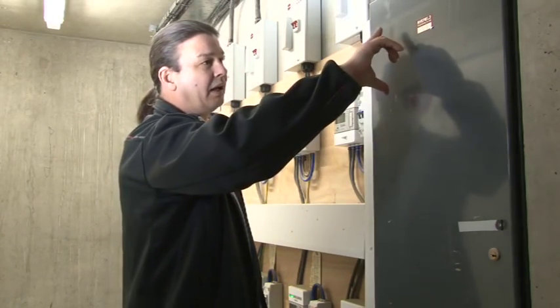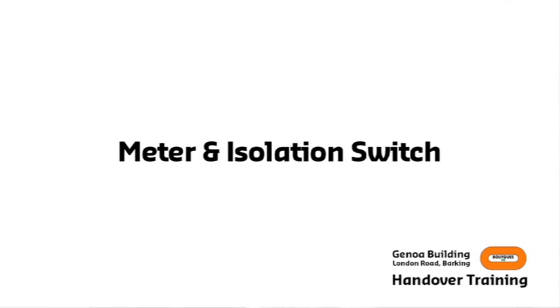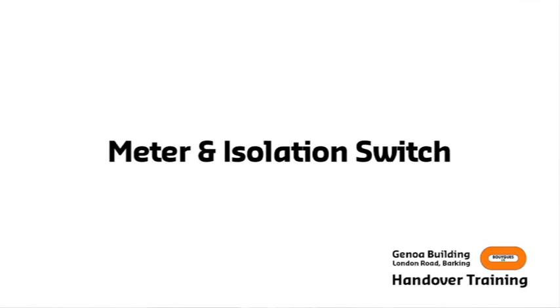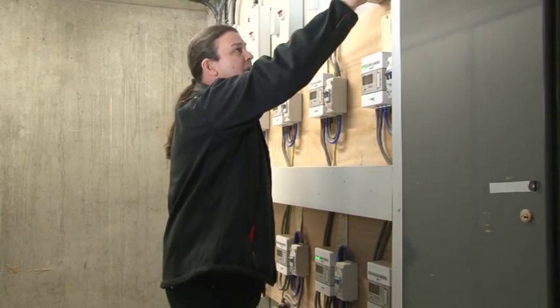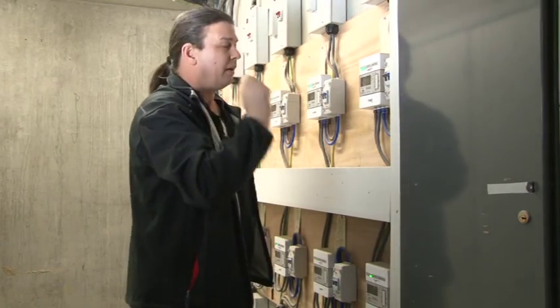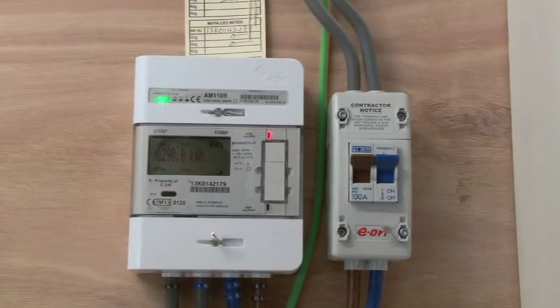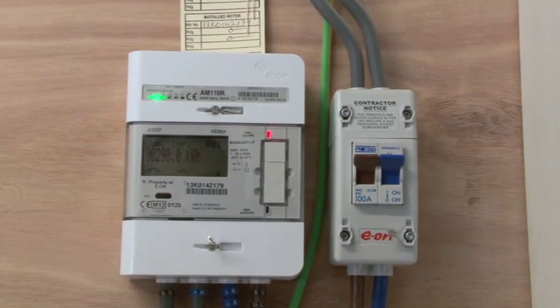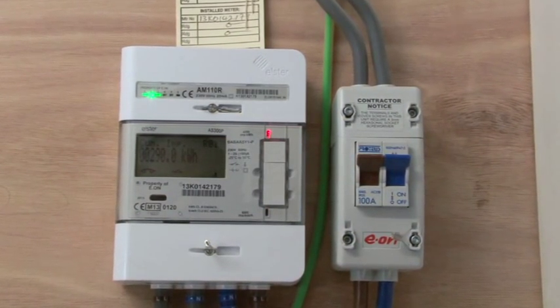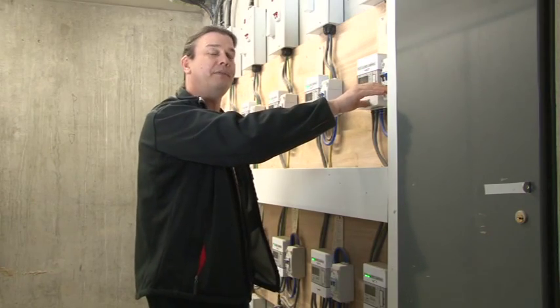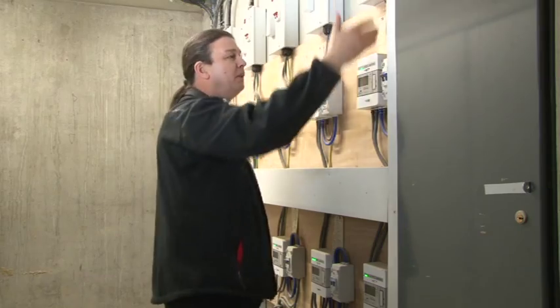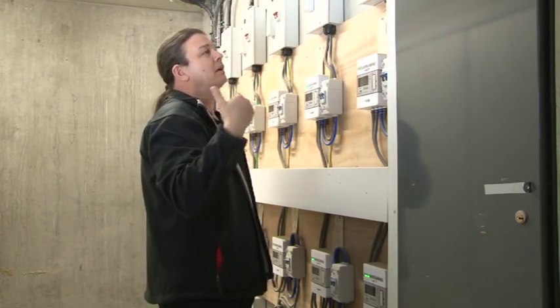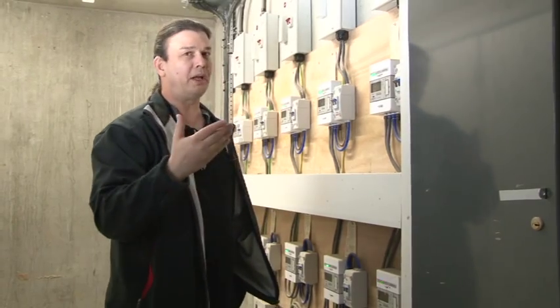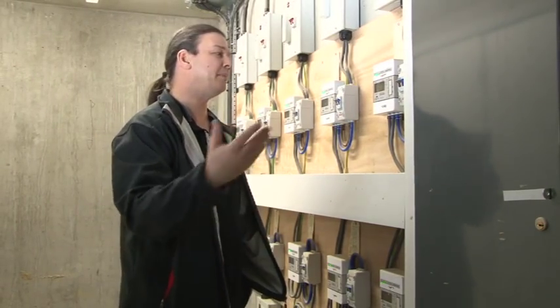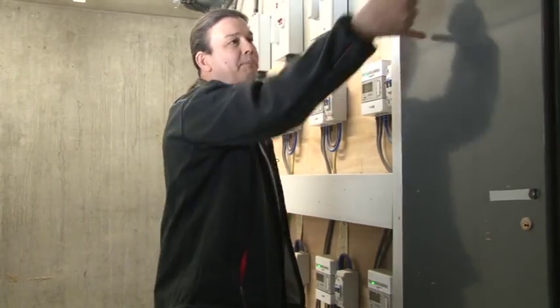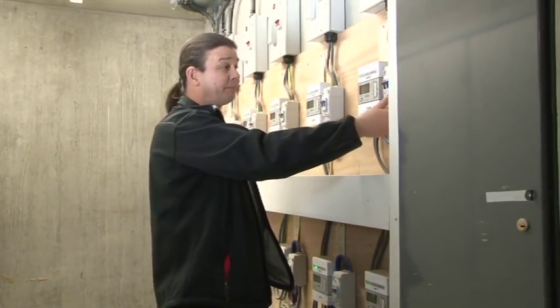From here, and there is a fuse for each flat, we then have a set of tails, as we call them, that run up through the meter, through an isolator, to a secondary isolator. E.ON, who provided the metering here, insisted that they have their own isolator switch. The rules of the Electrical Council state that I have to have an electrical isolation point, so we end up with a duplication, and that's all it is. If for any reason your supply is withdrawn, i.e. non-payment of bills, etc., that would be done from that point there, and this switch would be disconnected.